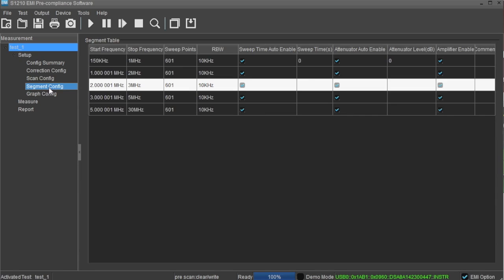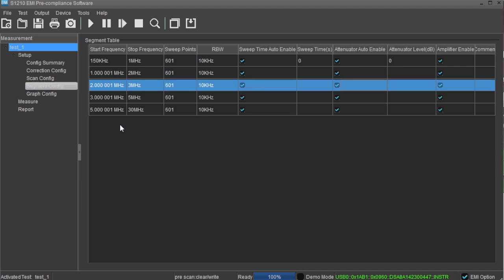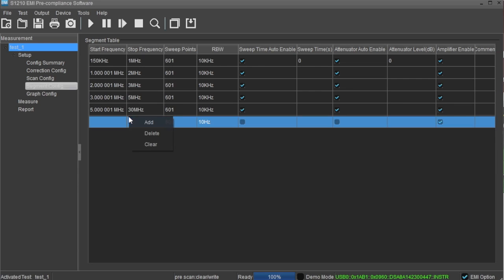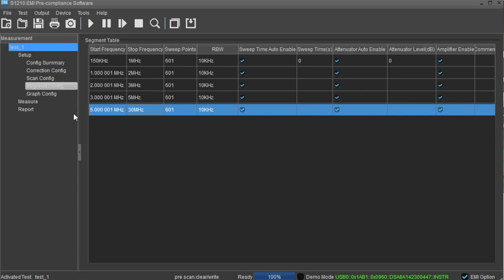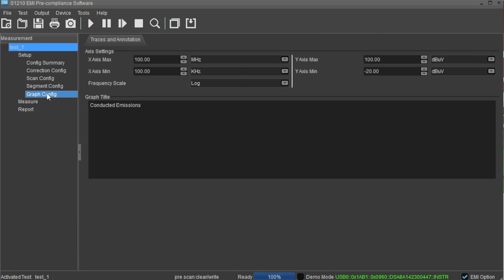The segment config area is where you can configure each scan segment. It contains the start and stop frequencies for each step, sweep points, as well as the resolution bandwidth setting for each step. You can add and delete segments by simply right-clicking in the segment window and then entering the proper values in each field. The graph config area contains the axes control for the graphical display of the data. You can set the maximum and minimum values as well as set the frequency scale for log or linear. You can also set the amplitude units as dBm, dB microvolts, dB microamps, or dB picowatts.